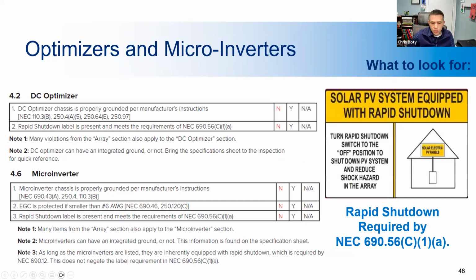All right, as I mentioned, one way that DC optimizers and microinverters are similar is the rapid shutdown features. So rapid shutdown is a method in the code where DC conductors are shut down on a level close to the array. If power is interrupted, the system shuts down to prevent live DC conductors in the system or the building. And this is allowable to use in the code as the method for rapid shutdown, right? You don't have to install additional things to achieve that requirement if your system has microinverters or DC optimizers. And so here you can see an example of the proper labeling to meet the rapid shutdown requirements of the system.